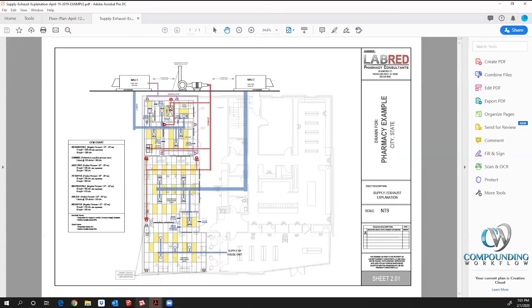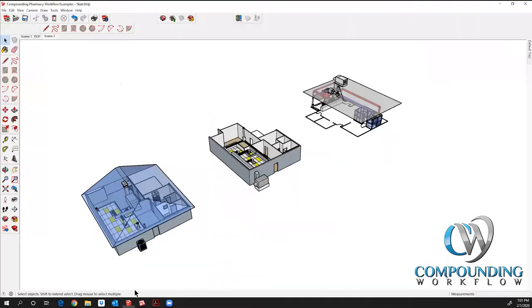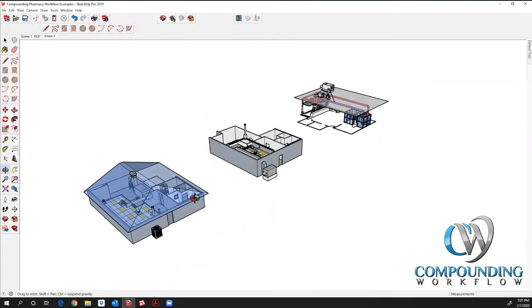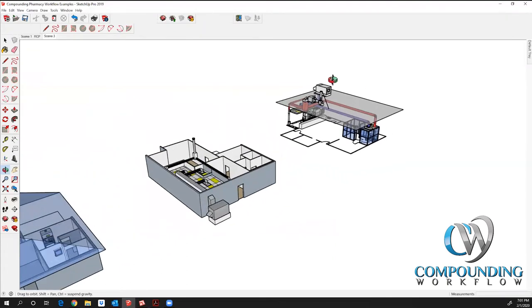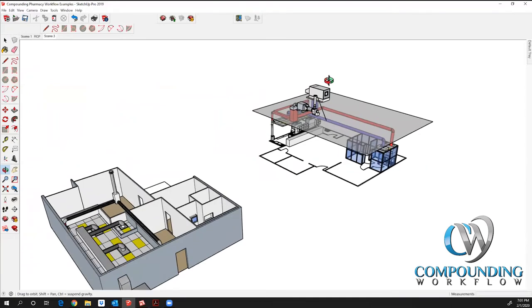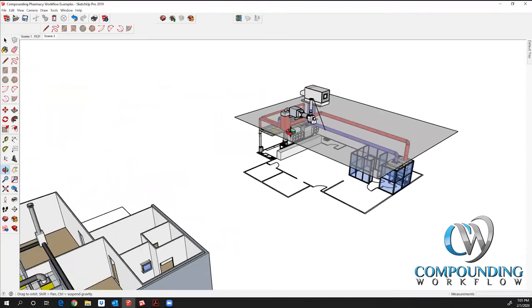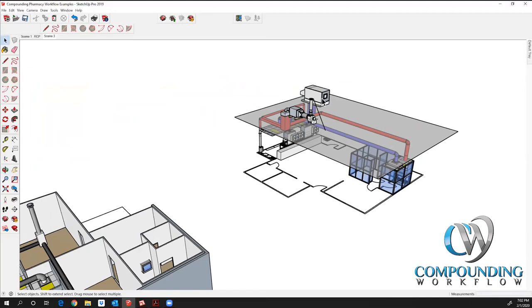I just want to briefly give you another piece that we sometimes do for projects, just to help mechanical engineers better understand the process. There are different ways to move air. With USP 800, we're basically externally venting the air, which means we're taking all of that air and we're taking it out of the building. We have to replace that, and more times than not, that takes a dedicated makeup air unit.